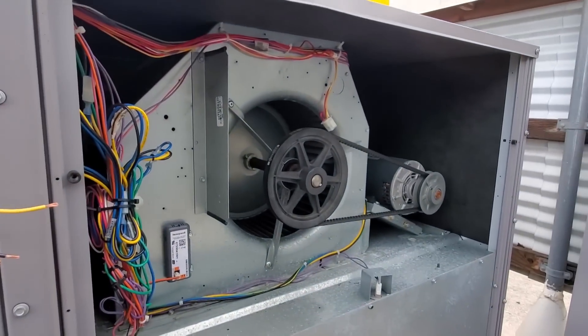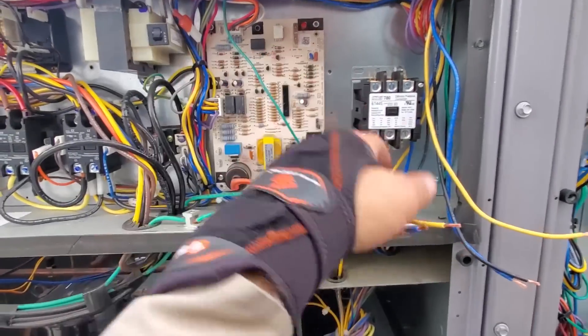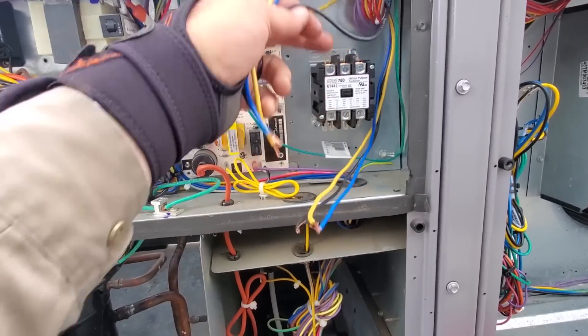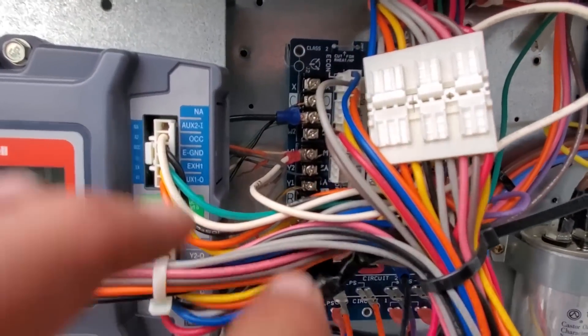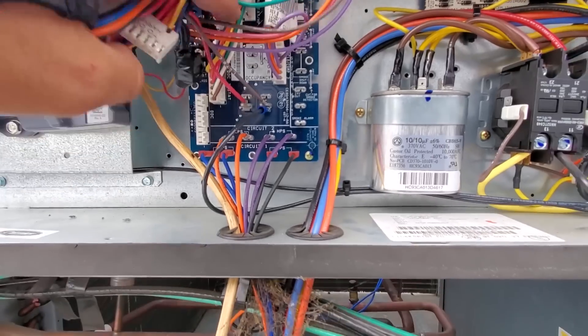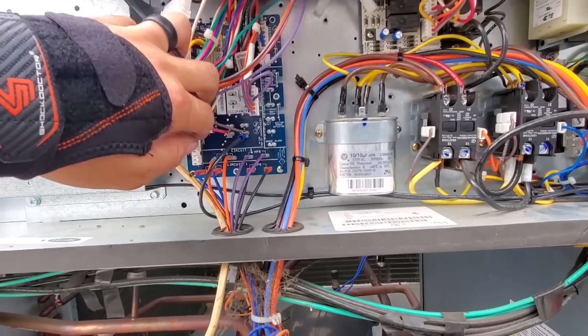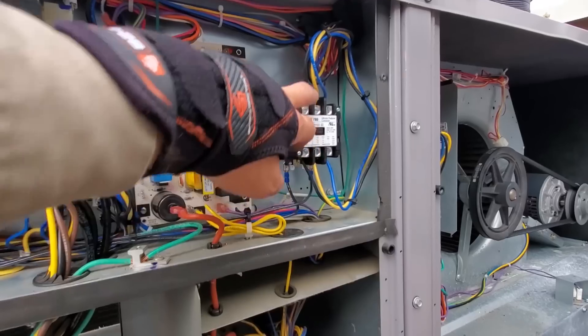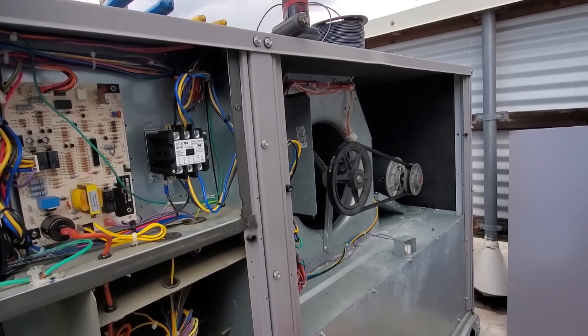So this is my other unit — pretty much the same thing. Just taking me a lot less time because I just jump in here. The first unit I was working on is right over there. All I did was pull the wires — there was a bunch of extra wire — pulled it up and over, line voltage in the top, load voltage out the bottom, bring coil voltage over from here. Same thing and we'll be good to go. One wire for the contactor coil goes to the G terminal, the other wire goes to the C terminal. I like that these boards have R and C terminals so you can get 24-volt power for various things — duct detectors and all kinds of stuff. Zip tied it carefully so it's not going to rub out, going right over to the contactor coil. Went color for color on the contactor. We're going to fire it up and test — I've got to tie up those plugs so they don't get sucked into the blower.